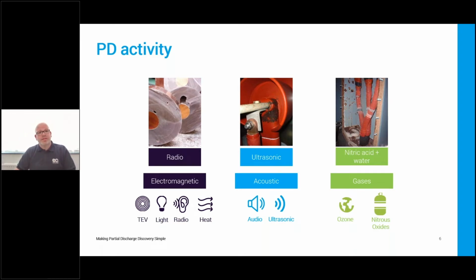If we move to the center picture, surface discharge causes sound. So again, when the EA engineer is carrying out a PD survey, or you're using an UltraTEV, when you're looking for surface discharge, you're checking for ultrasonics, sound. The middle picture there shows some evidence of surface PD activity. The picture on the right shows evidence of PD within a HV termination box.